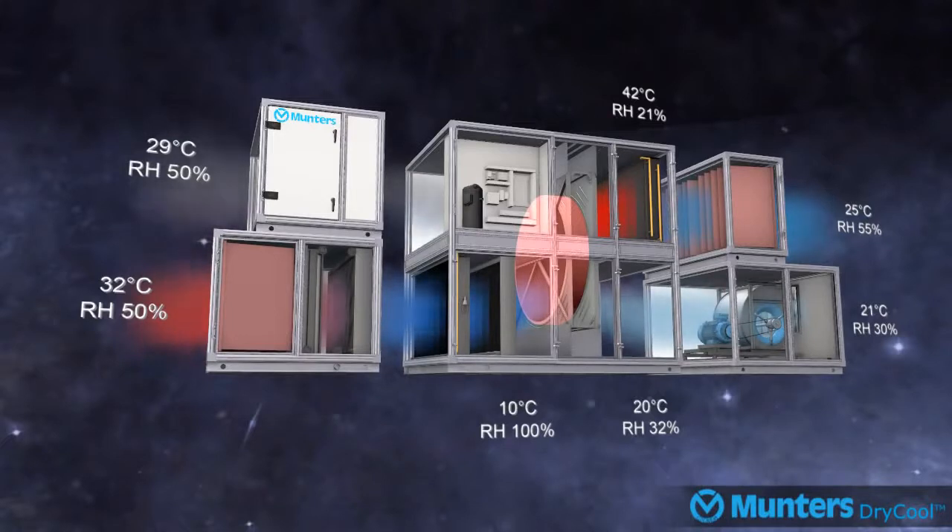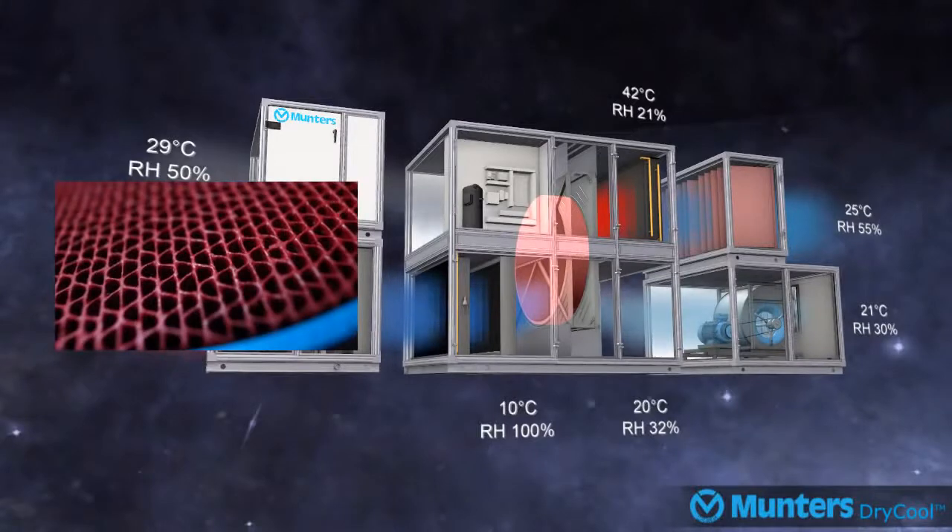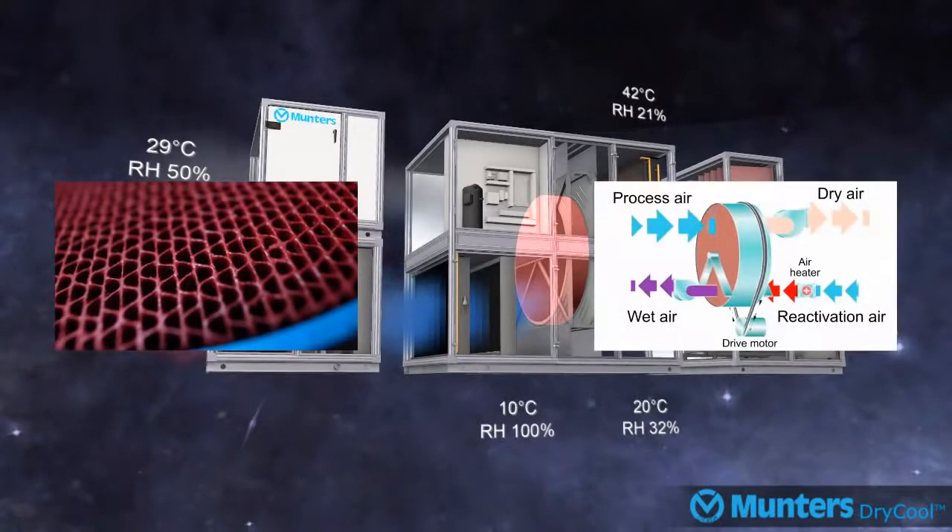Munters desiccant drying wheel operates by passing the supply air stream through a slowly revolving desiccant wheel. The slowly revolving wheel continuously passes a desiccant segment with accumulated moisture through a reactivation sector air stream, where the recovered heat from the dry cool process is used to drive off the accumulated moisture.